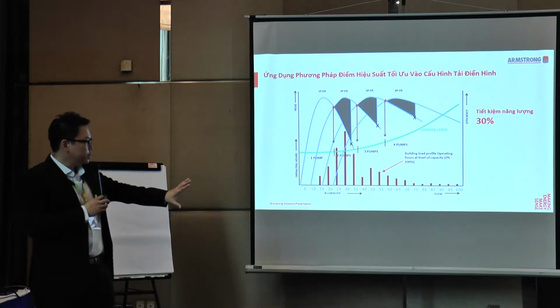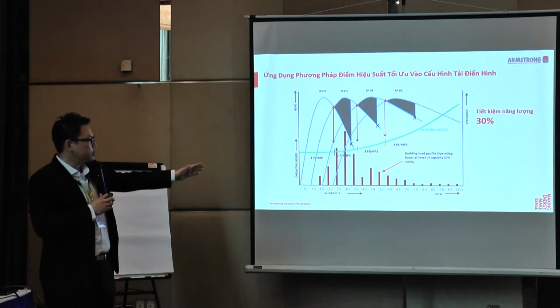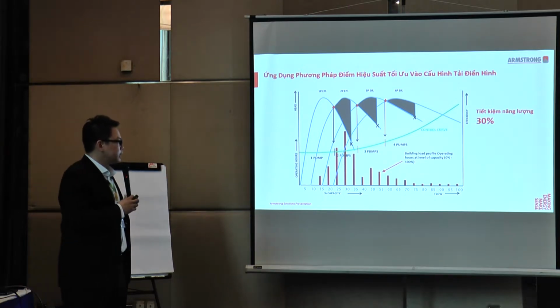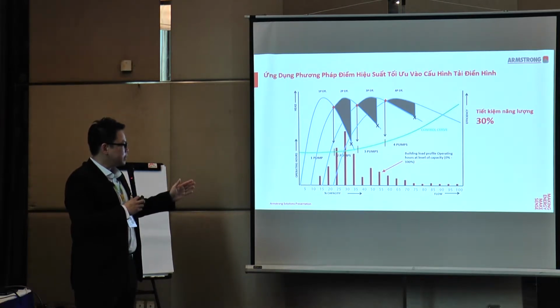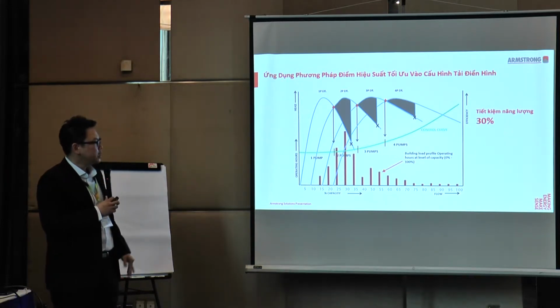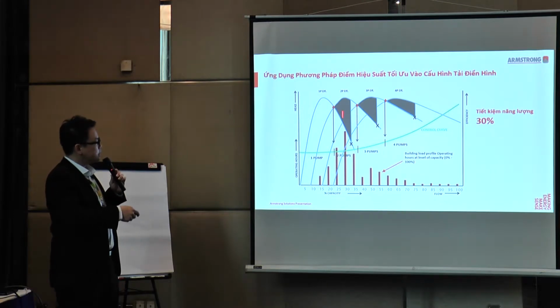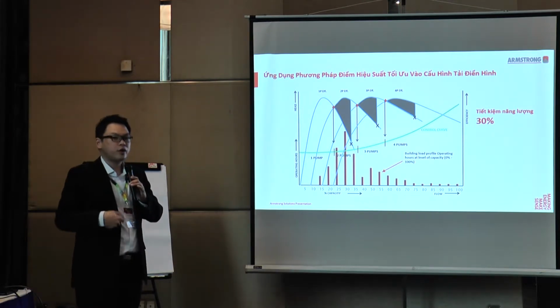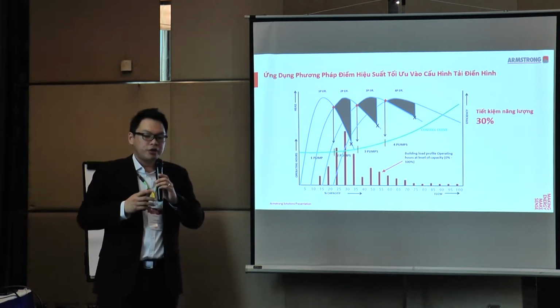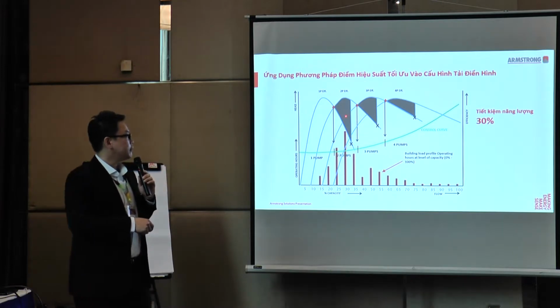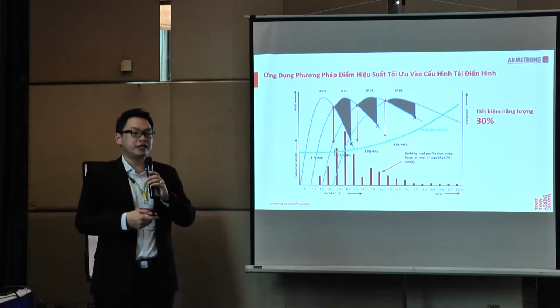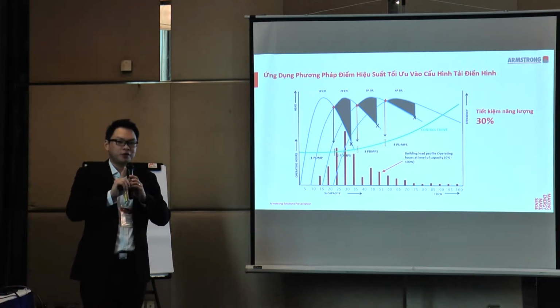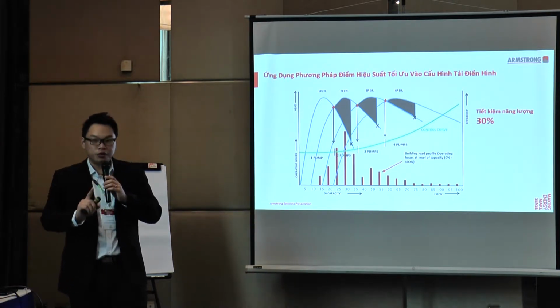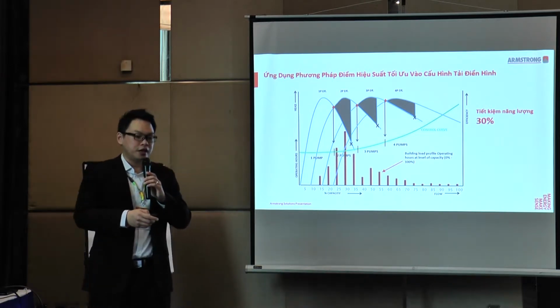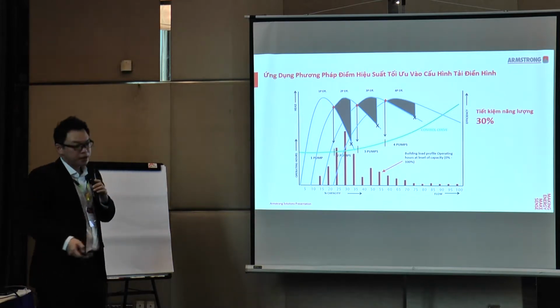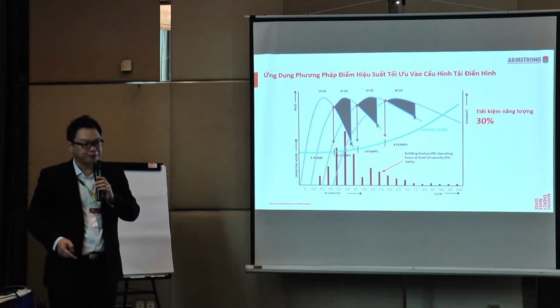If I integrate our building load profile, this is how it looks at the bottom of the bar graphs. You will see that between 25 to 35% of the capacity and also between 50 to 60% of the capacity, this is where it overlaps. What this graph is saying is that the majority of the time, where the building is most used, is also where the speed-based approach gives you the least efficiency. If you use the Armstrong methodology, it gives your clients better efficiency readings. So we say there are 30% energy savings from best efficiency staging.